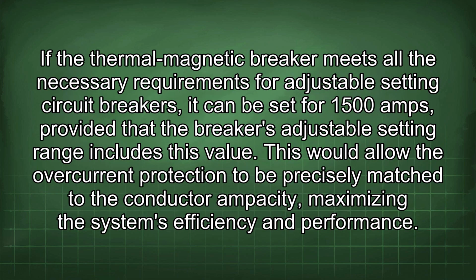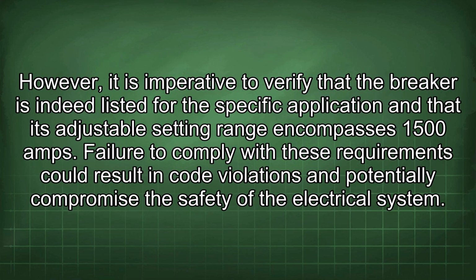If the thermal magnetic breaker meets all the necessary requirements for adjustable setting circuit breakers, it can be set for 1500 amps, provided that the breaker's adjustable setting range includes this value. This would allow the overcurrent protection to be precisely matched to the conductor ampacity, maximizing the system's efficiency and performance. However, it is imperative to verify that the breaker is indeed listed for the specific application and that its adjustable setting range encompasses 1500 amps. Failure to comply with these requirements could result in code violations and potentially compromise the safety of the electrical system.